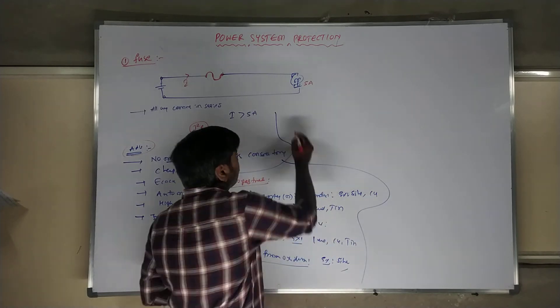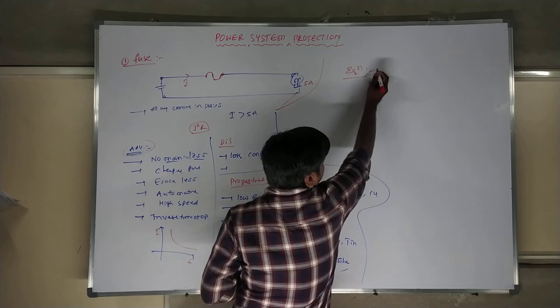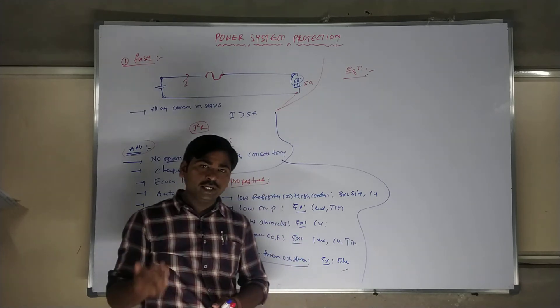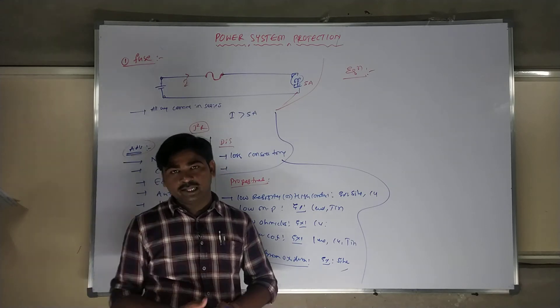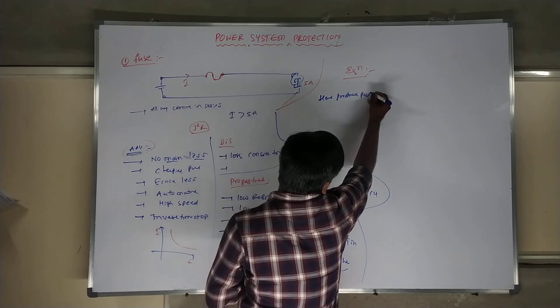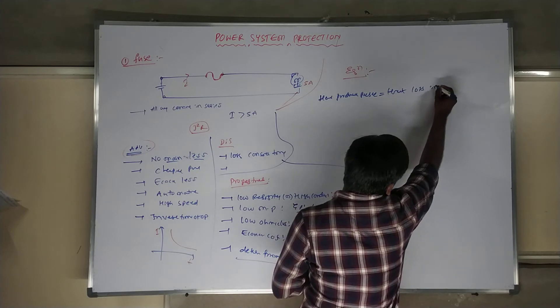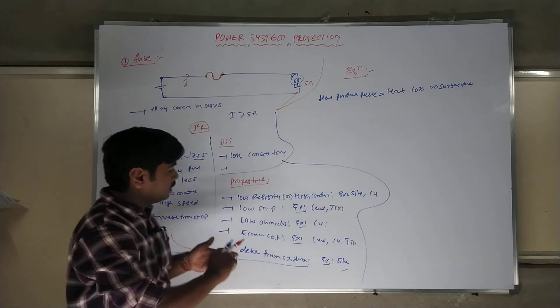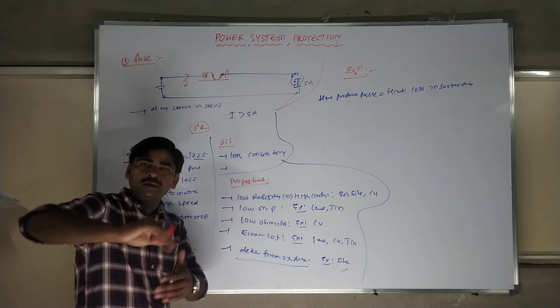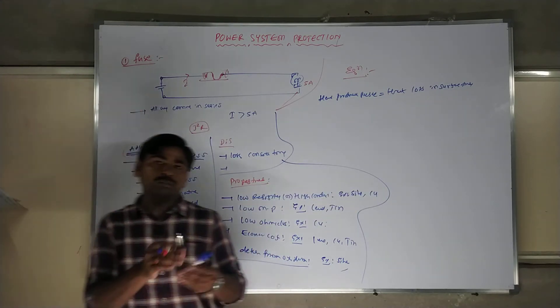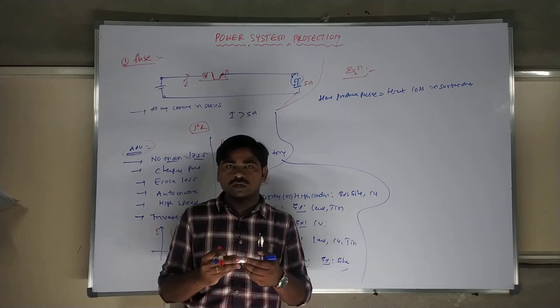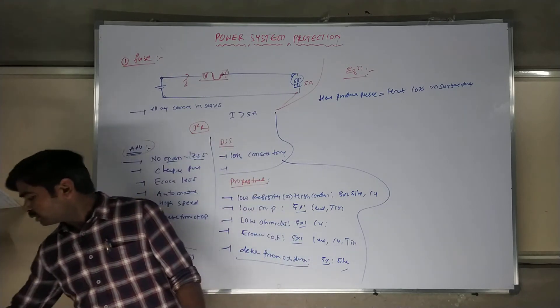Next, when you go for fuse operation, there is an equation required. When deriving the fuse current equation: the heat produced per second is equal to the heat lost through the surface area. When current flows through a metal piece having resistance, heat is produced (I²R). That heat is transferred through the surface area of the metal piece to the outside. Both must be equal according to the law of conservation of energy. So heat produced per second equals heat lost per surface area.